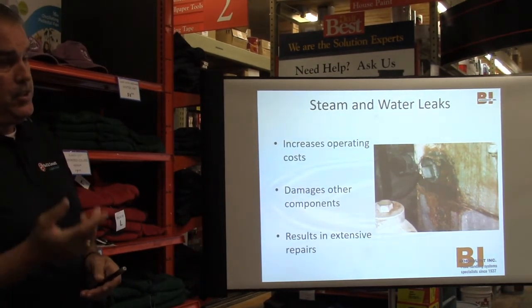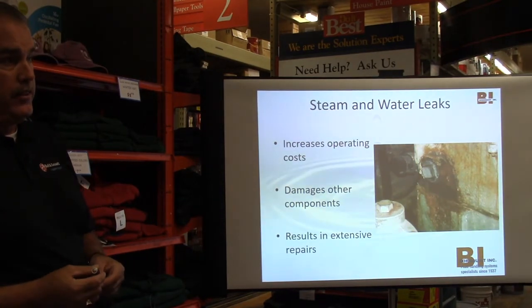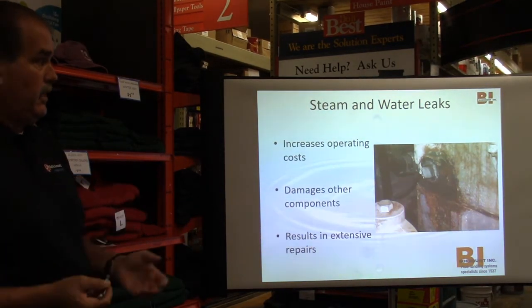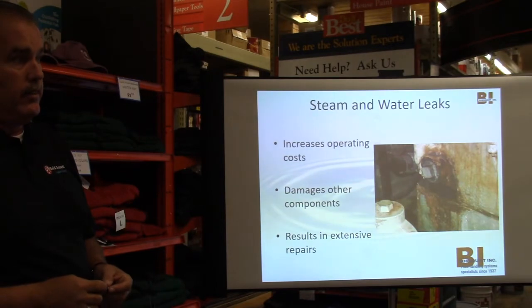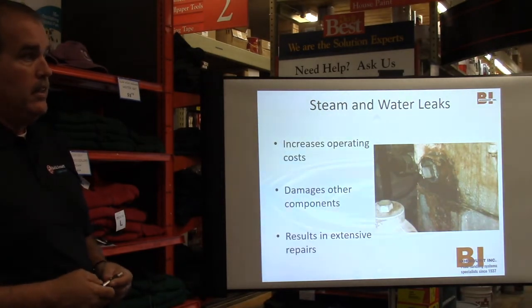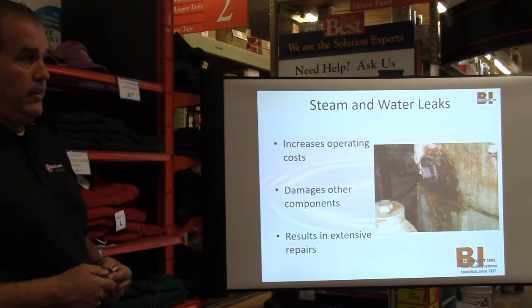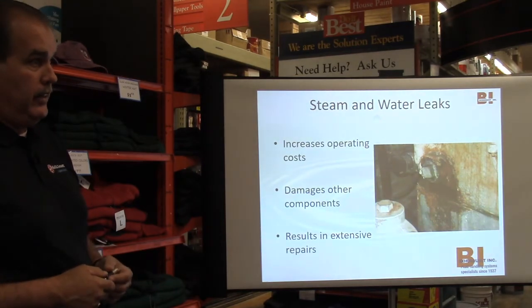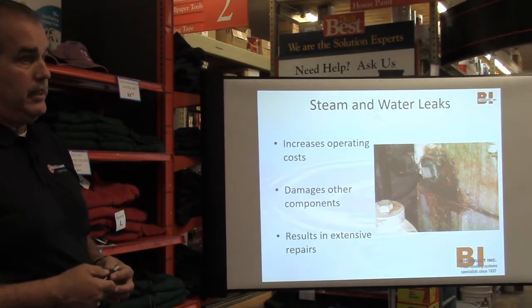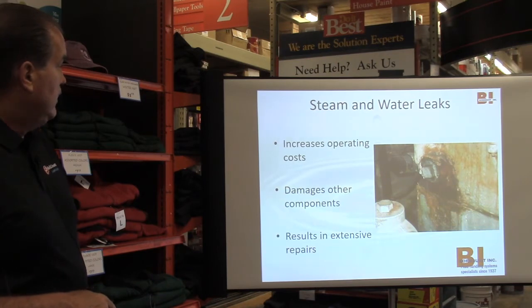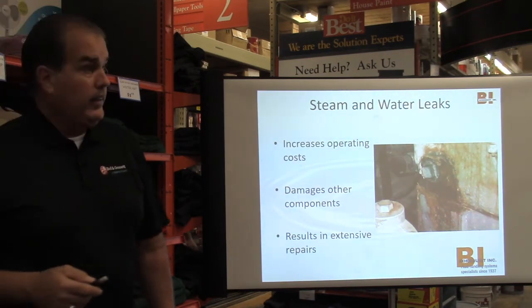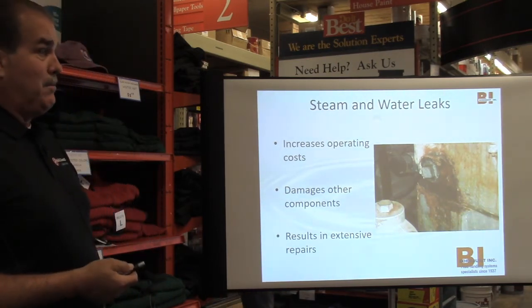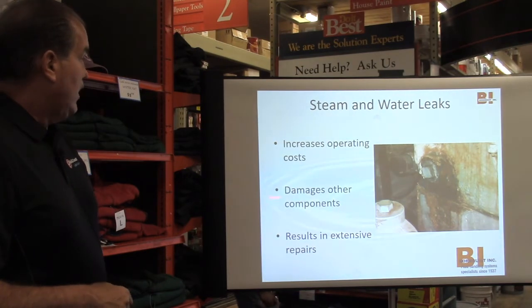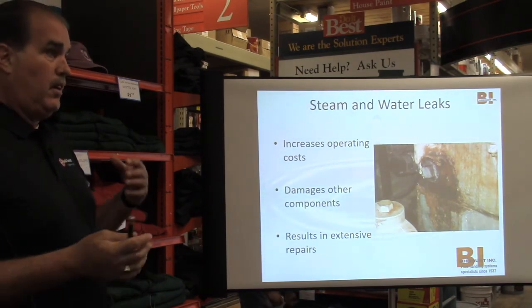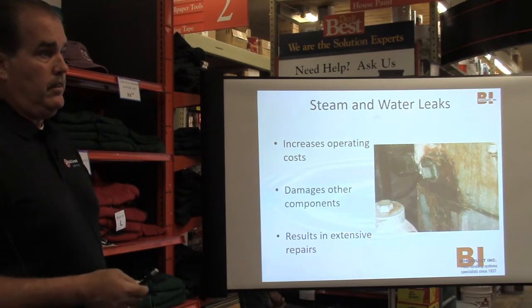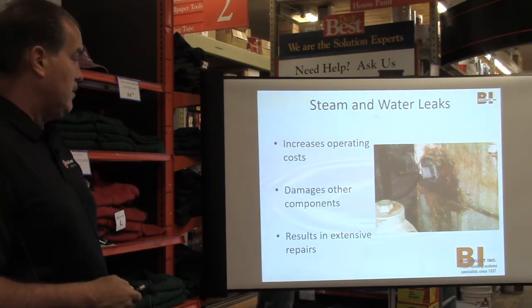And the unfortunate thing about that is if you have an underground leak, besides busting up the concrete and getting to it, you're in trouble because there's really no easy answer to that. If you're pretty comfortable you got a leak underneath, it's going to be expensive. Well, yeah, finding it is, that's what I'm saying, if you truly have determined it. And the leak can damage other components by bringing in all the dirt, and with the system, you want to keep it as clean as possible.